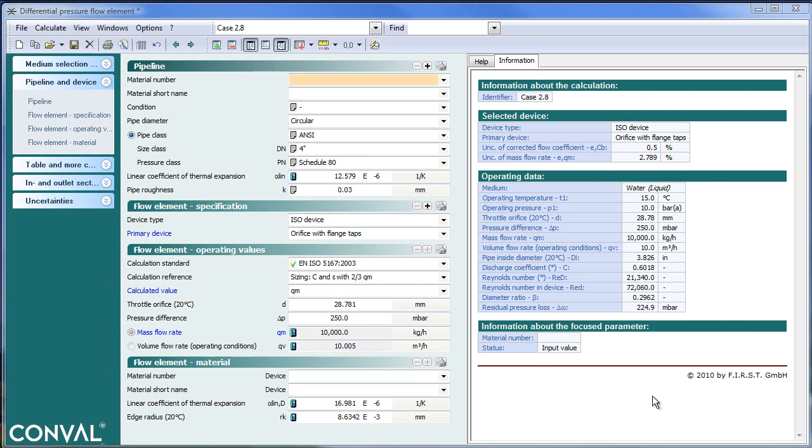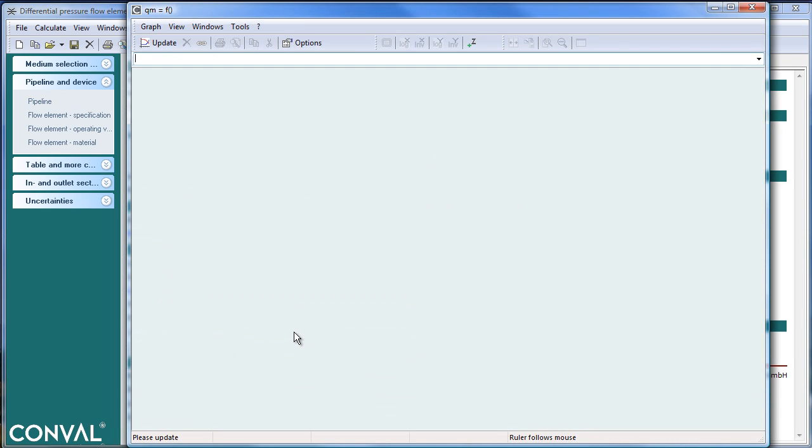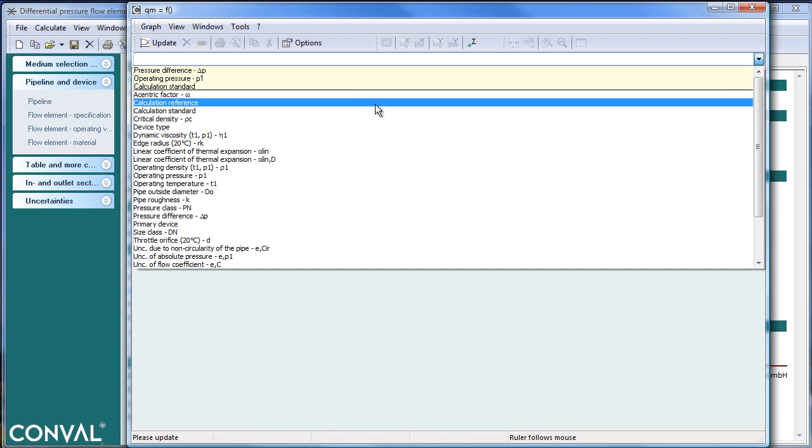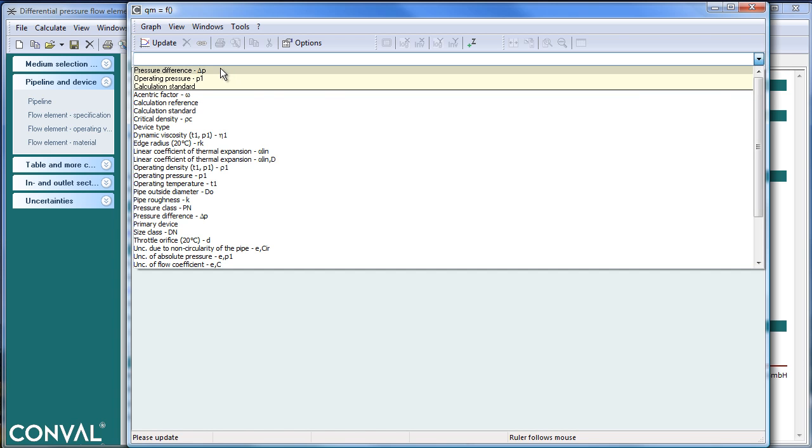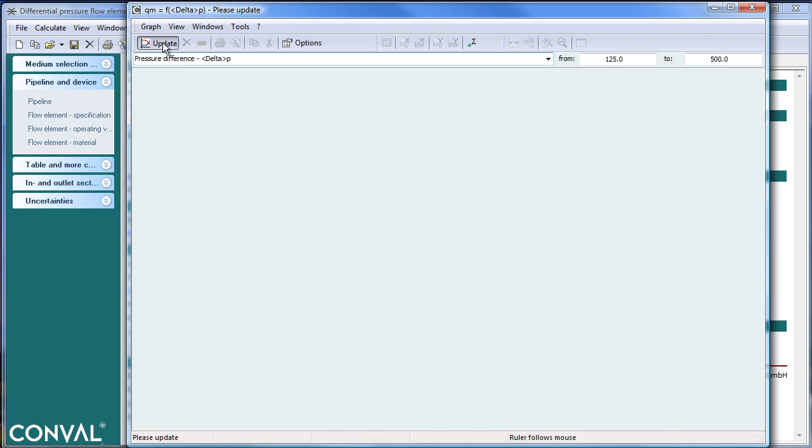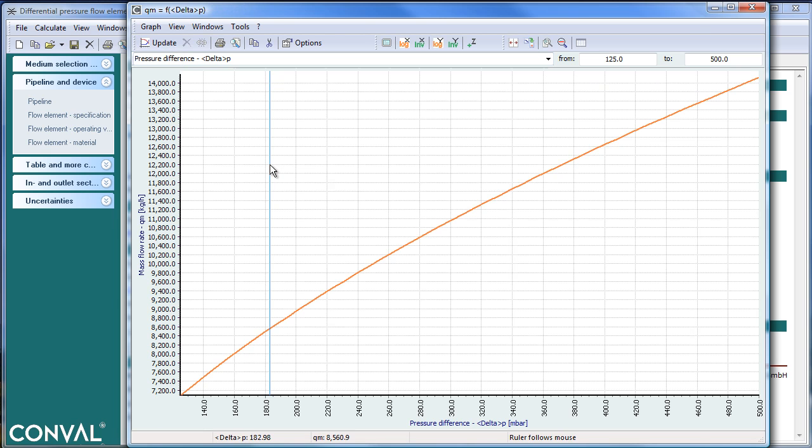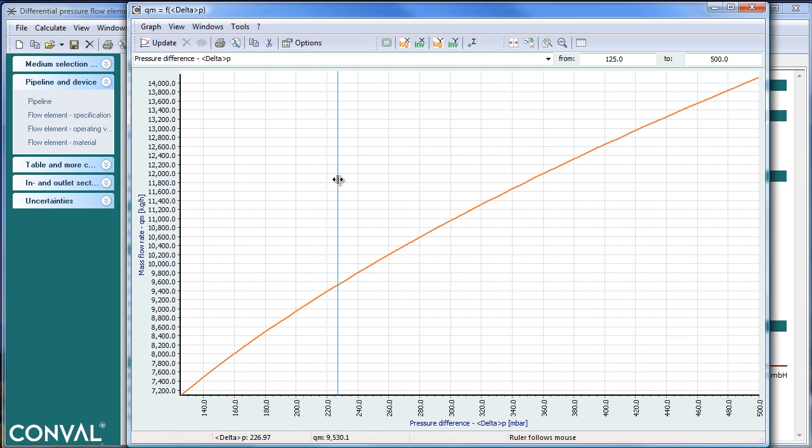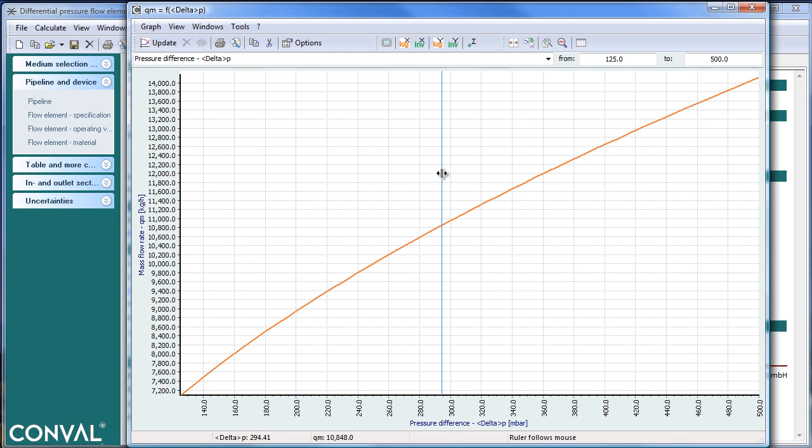XY or XYZ plots can be generated for any parameter having a calculator icon because it's a calculated value. For example, the mass flow rate for an orifice calculation has a calculator icon. When you click it, a pop-up screen appears with all possible parameters influencing this mass flow rate. The most obvious one is the delta P. If you click update, you get a plot, which is a typical Conval curve showing Qm in function of differential pressure.